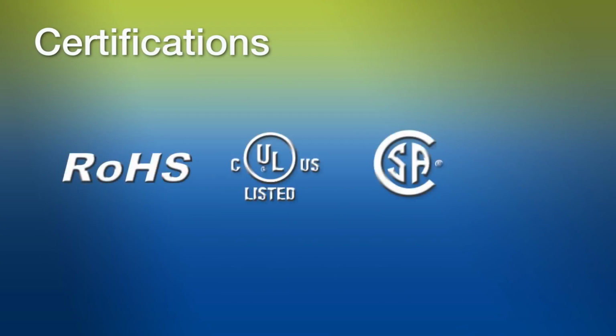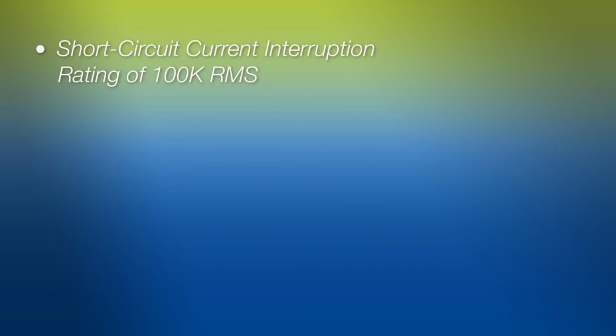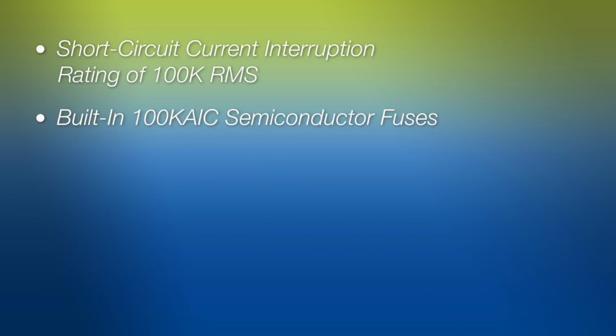Certifications for the Z1000U package include RoHS, UL, CSA, and CE. The Z1000U has a short-circuit current interruption rating of 100K RMS. Built-in 100 KAIC semiconductor fuses provide the highest level of branch circuit protection.